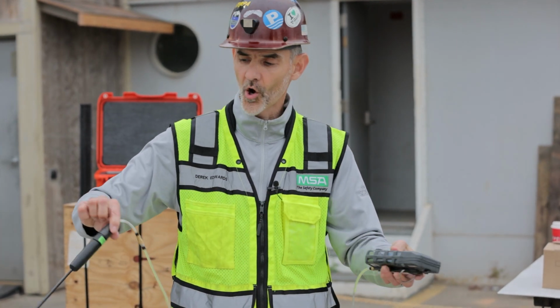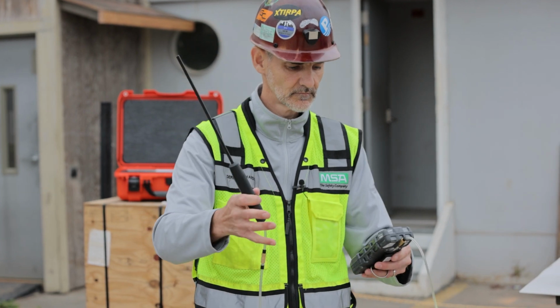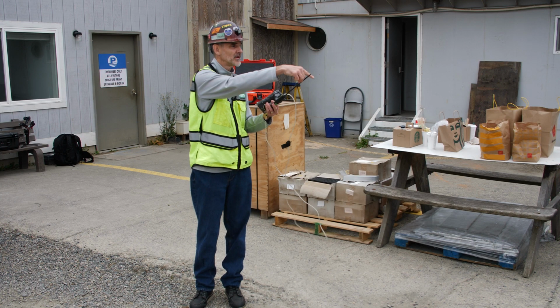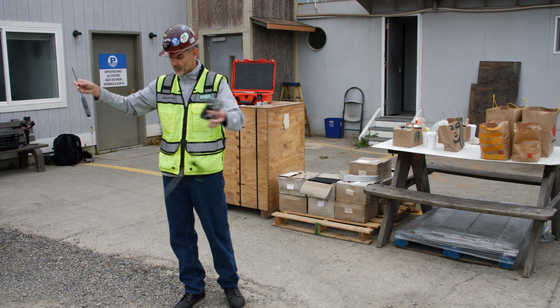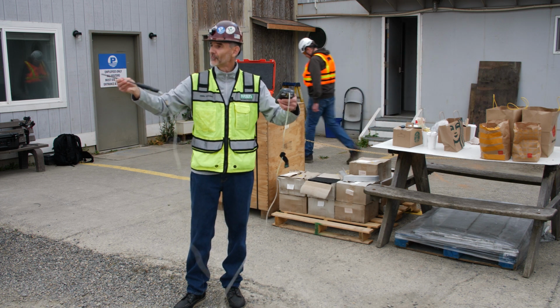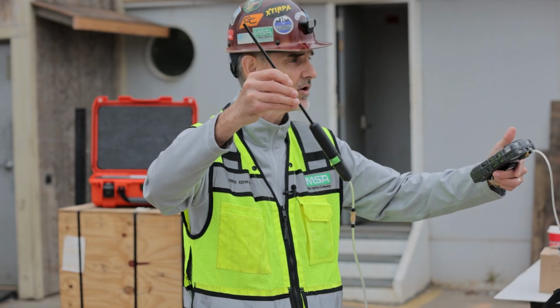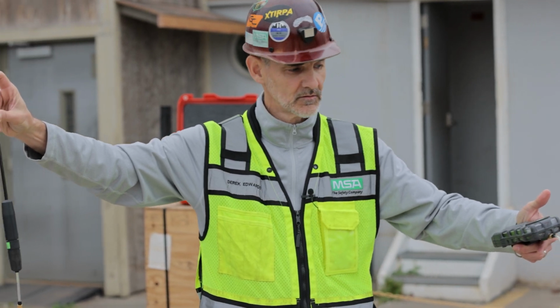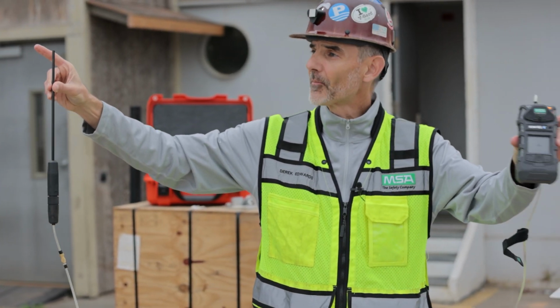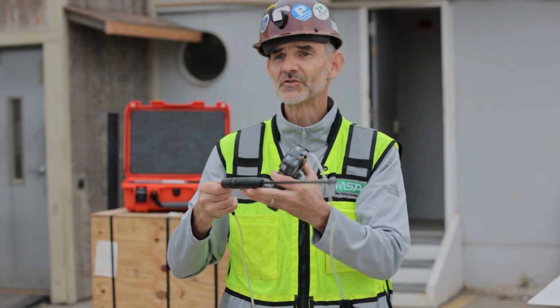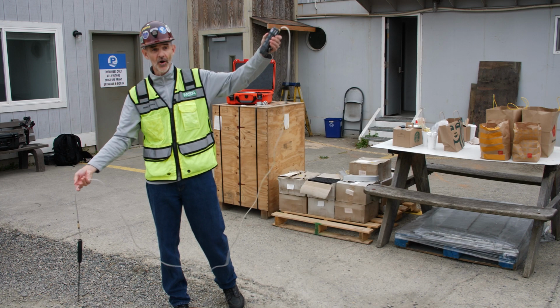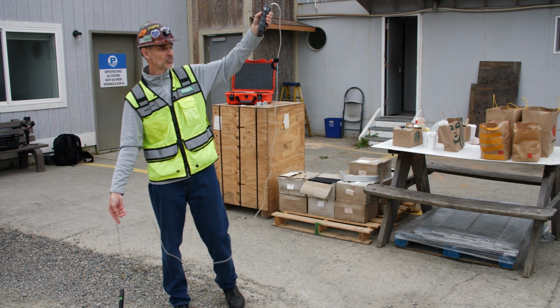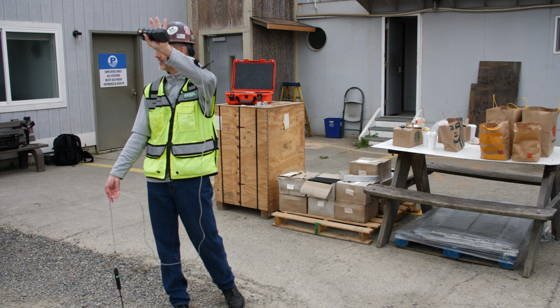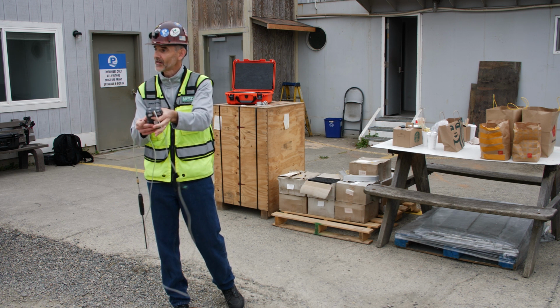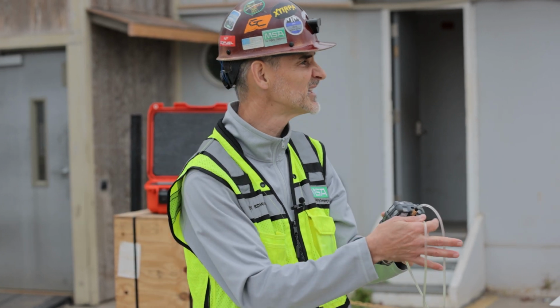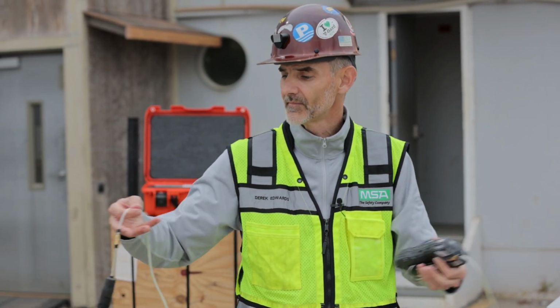Again, a quick connect on our probe. And now we are pulling a sample from here. Remember I mentioned earlier that if we are pulling a sample, which you typically are, before you turn the instrument on, connect this up so that we can test the whole system. I will now block the end of this, it's going to send our pump into pump alarm. So if I drop this into a space that's got water at the bottom, it's going to block that sample system, and this is what's going to happen. Or if we kink this hose, we simply, again, read the screen, we press the right button, it says reset, and we go back to work, okay?